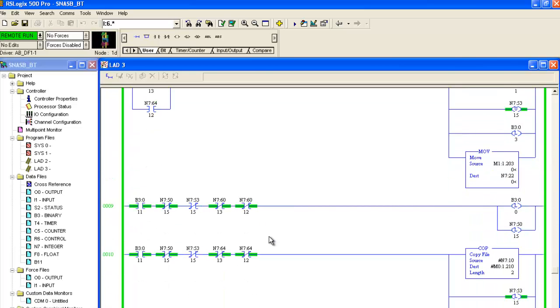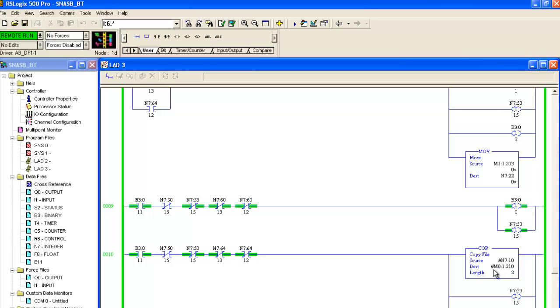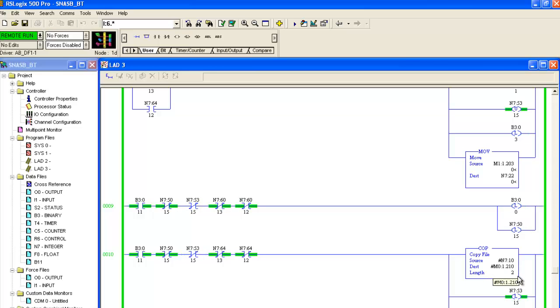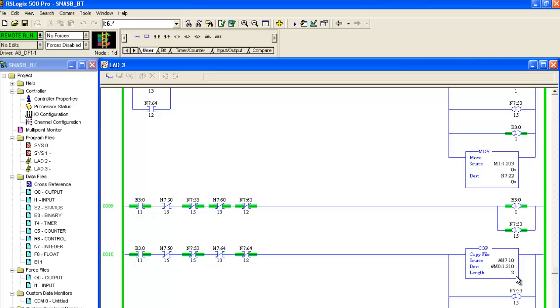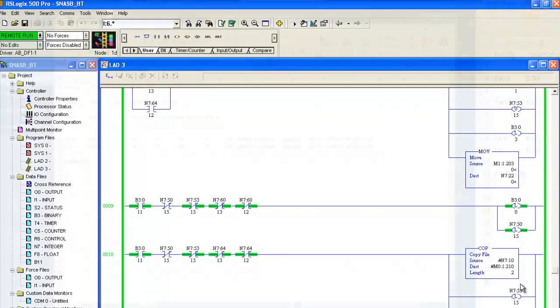M1 is input data, M0 is output data. The copy statement is copying two words from our N7 file to the scanner card M01210, and then out to the remote IO network.